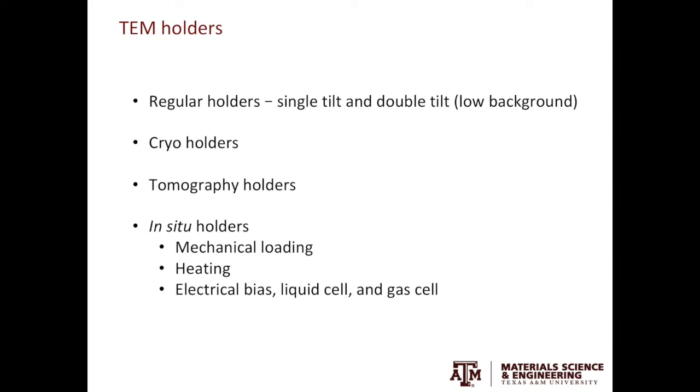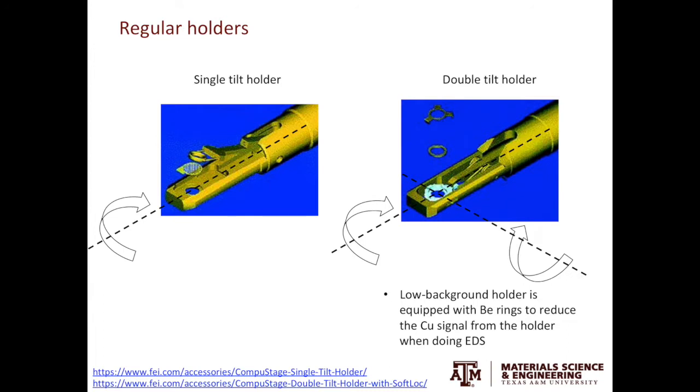Let's look at each type of holder one by one. For the regular holders we have the single tilt holder and the double tilt holder. You have the TEM specimen here and you lower the clamp ring to secure the specimen. You can tilt the specimen along the long axis of the holder, so it's the single tilt holder.